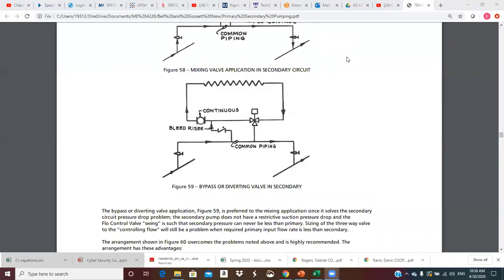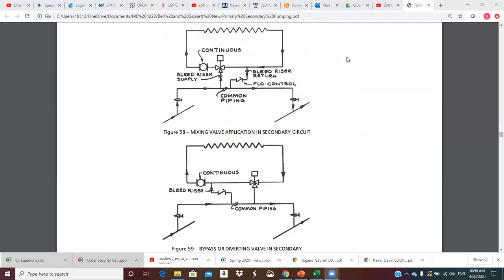The bypass or diverting valve application in figure 59 is preferred to the mixing application since it solves the secondary circuit pressure drop problem — that big pressure drop on the suction side of the pump. Also, the flow control valve opening is such that secondary pressure can never be less than primary pressure, because whatever pressure exists can be transmitted through the valve. This becomes kind of like the point of no pressure change. There's not much flow through that valve, so it's pretty close.